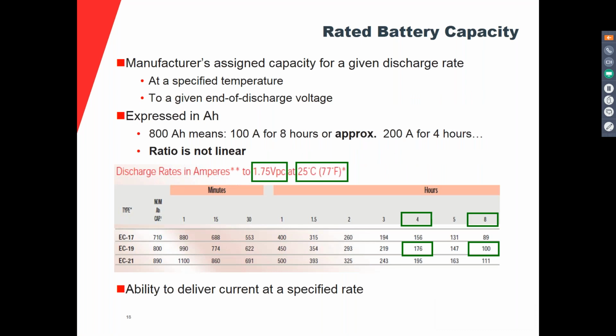Okay, so we already defined battery capacity, and now we need to see this from the perspective of the manufacturer, the rated battery capacity. We already talked about the capacity that is needed in the substation and what we need to do to verify this capacity. But then when we purchase a battery, we need to know its rated capacity. This is a value that is assigned by the manufacturer through the manufacturing process, and it is given for a specific temperature and a specific end of discharge voltage.